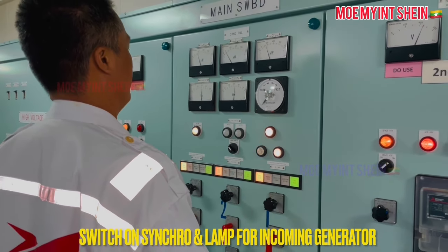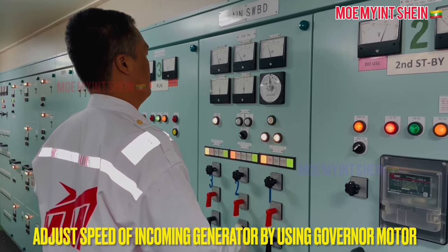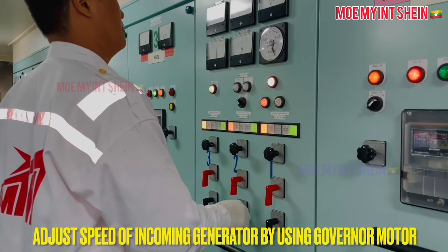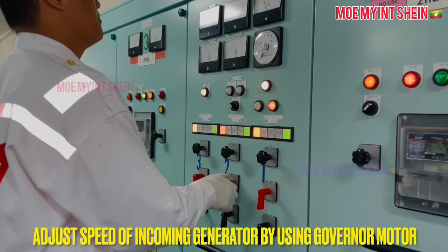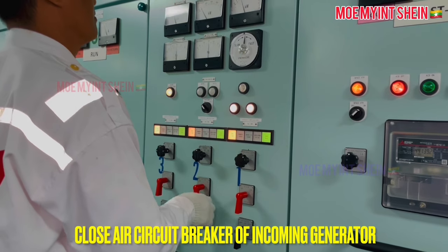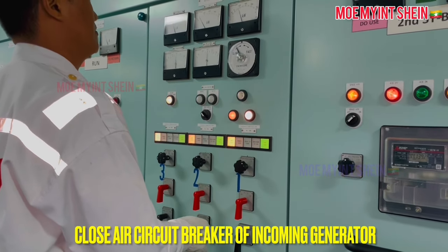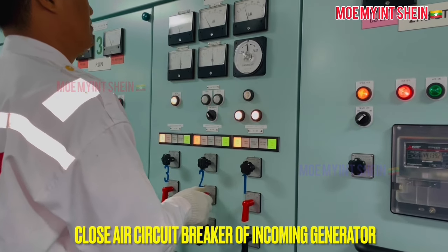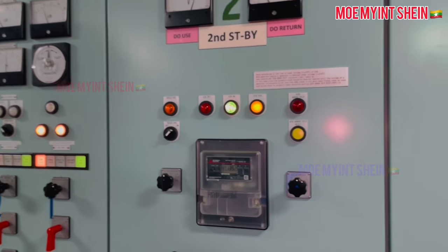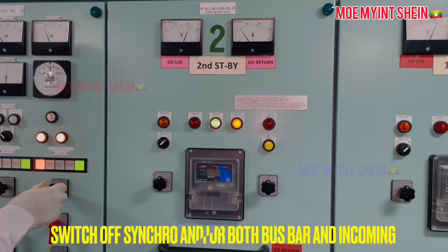Adjust the speed of the incoming generator engine by its governor motor. When the pointer of the synchroscope reaches the 11 or 12 o'clock position, pull the handle and turn in the close direction of the air circuit breaker. After then, don't forget to switch off the synchro and lamp.